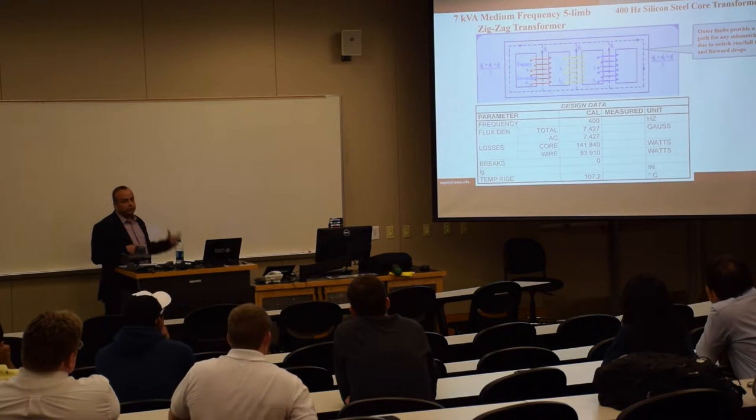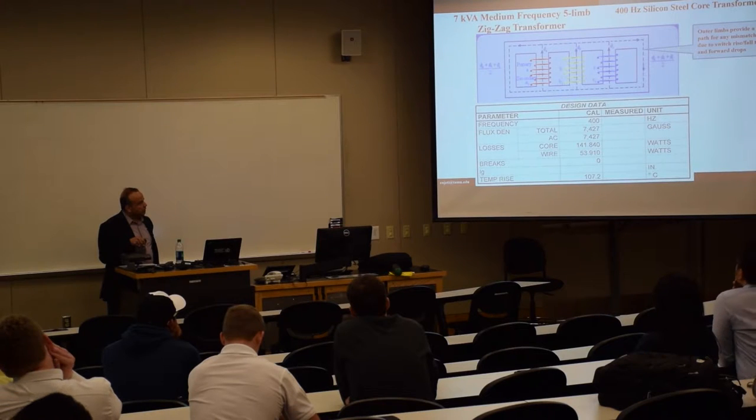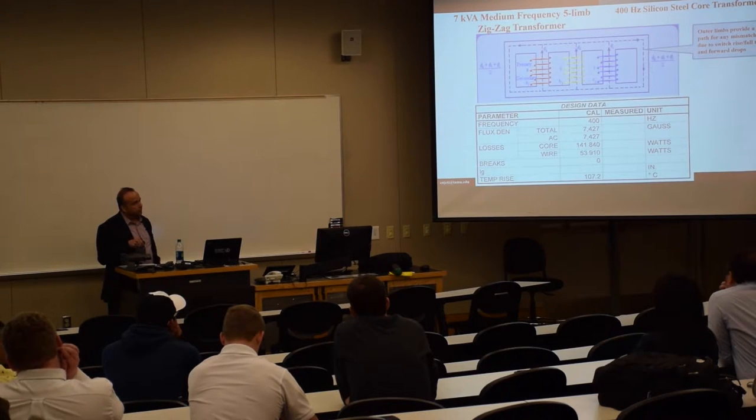Contrary to a three-phase transformer with only three limbs, we thought we needed five limbs because when you switch this winding and this winding and this winding with converters, the on drops and conduction drops, as well as the rise time and fall time, may have mismatches. So the flux may not all add to zero, instant to instant, and we'll get some irregular voltages and so on. So we put the fifth limb, an outer limb, to provide a flux path due to switch rise and fall times. We also put a search coil there to see what's going on. So that's been our design on that transformer.